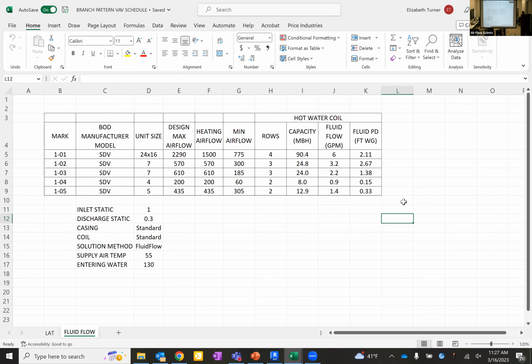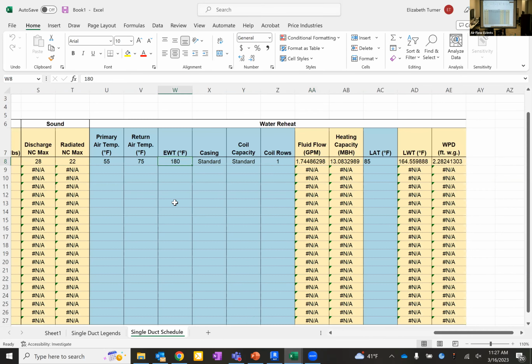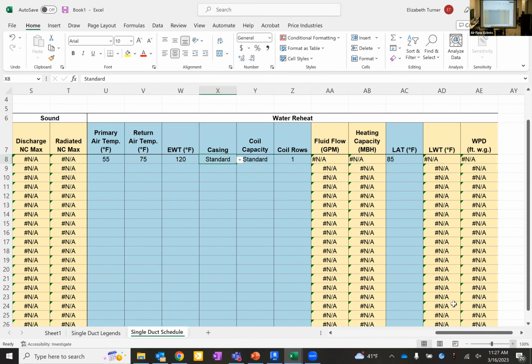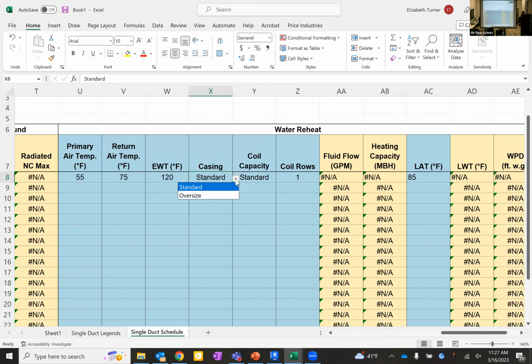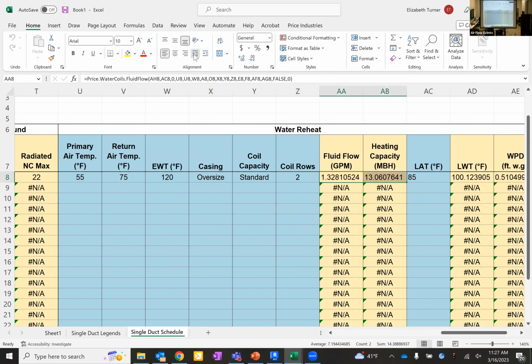Yeah, it's pretty easy to pick VAV boxes when you've got 180-degree water. You can fall out of bed and kind of guess and you're pretty safe. But with a lot more heat recovery chillers and lower water temperatures and condensing boilers, being able to design around 120 or 140 is really challenging for bigger boxes. You end up with these decisions about, well, using high capacity 12 fins per inch coils. Well, that's great, but now I don't like my leaving water temperature, and my condensing boiler doesn't like big temperature swings. So you go back and forth and back and forth.